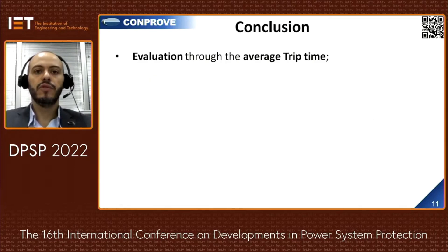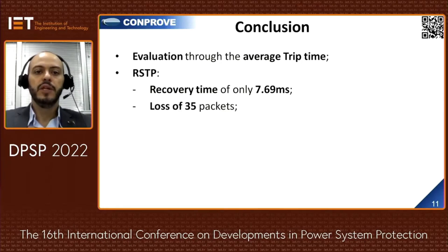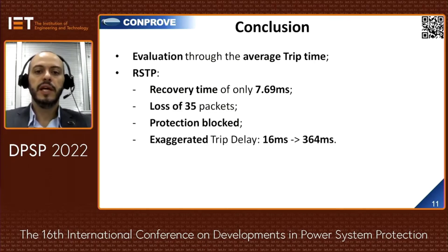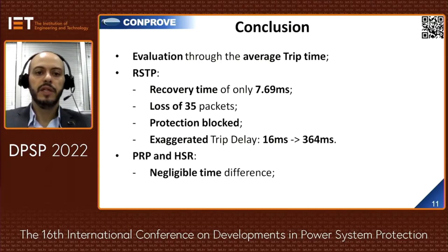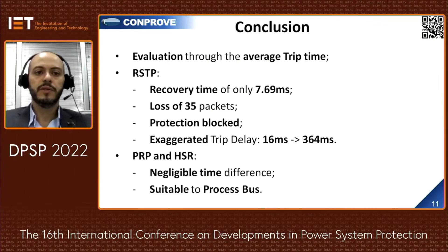As the conclusion for this paper, we performed the evaluation through trip times. In the RSTP case, the recovery time was 7.69 milliseconds — 35 sampled value frames were lost, resulting in protection being blocked, with an exaggerated trip delay difference from 16 to 364 milliseconds without and with contingencies. In the PRP and HSR case, there was a negligible time difference, leading to the conclusion that these protocols are more suitable for the process bus. Thank you.